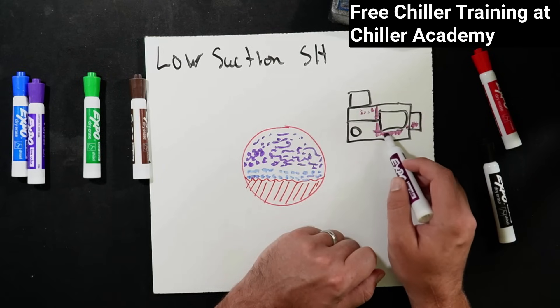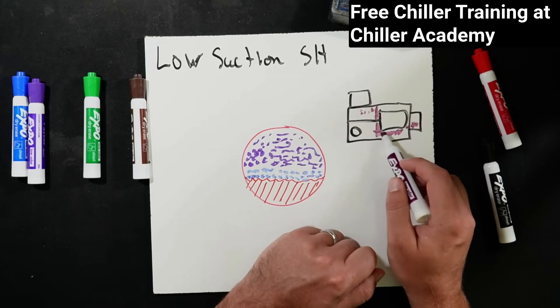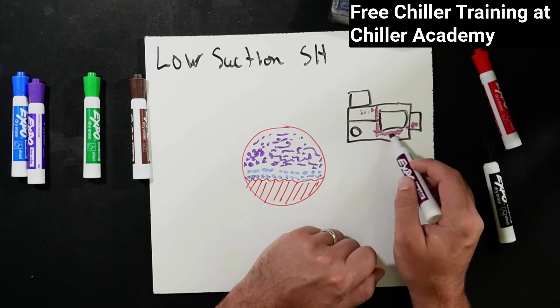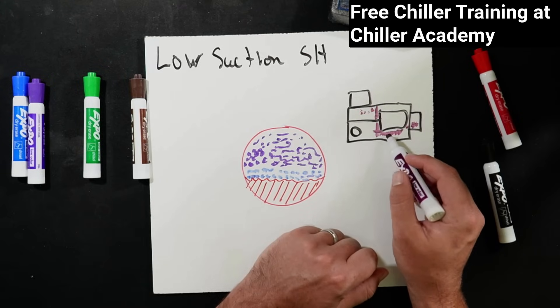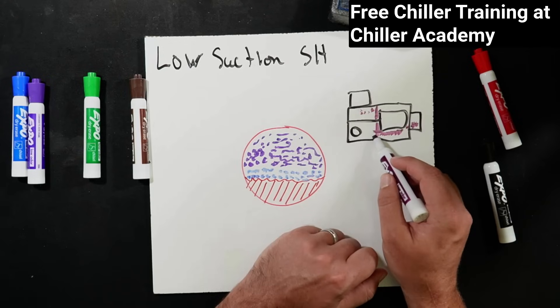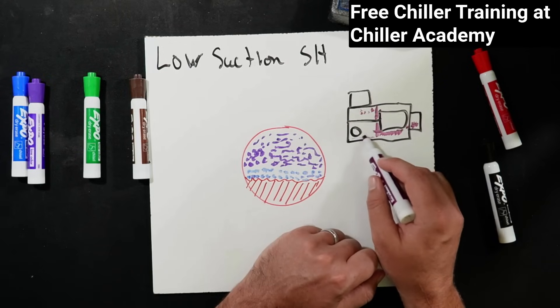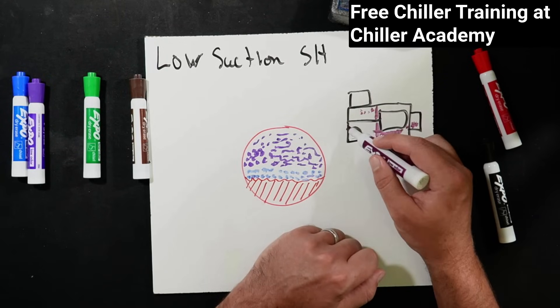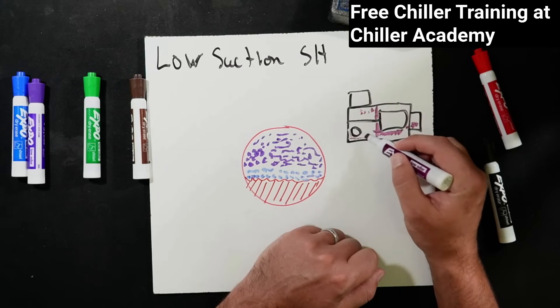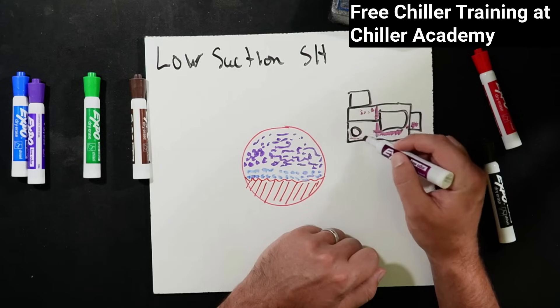Well, when liquid refrigerant starts to come in there, it now starts taking the path of that oil and liquid refrigerant is heavier than oil. It has a heavier specific gravity. And so it will start to collect down here, but our oil pump is also down here. So there's a lot of turbulence.